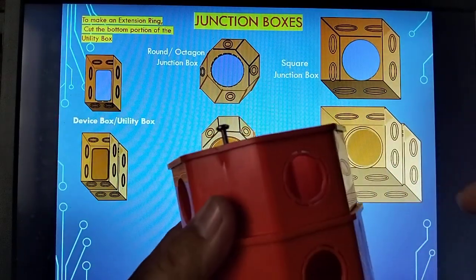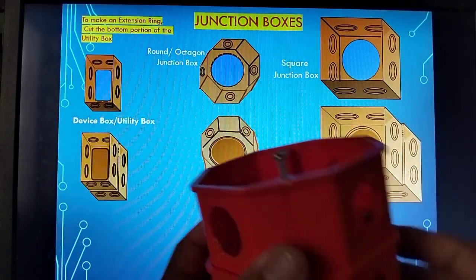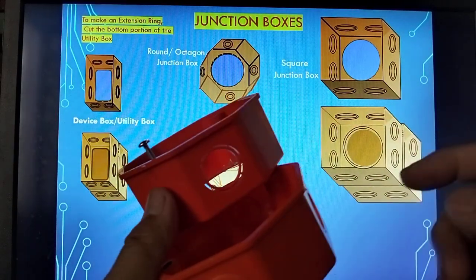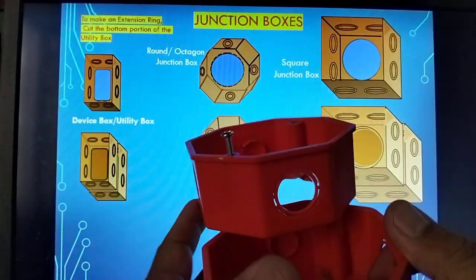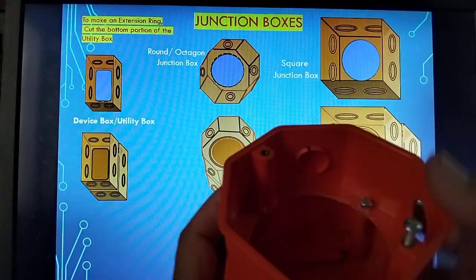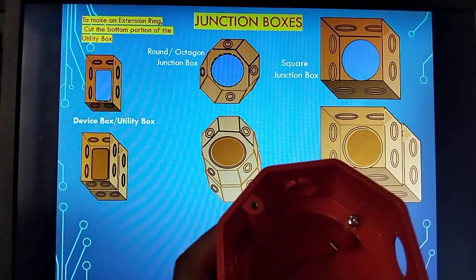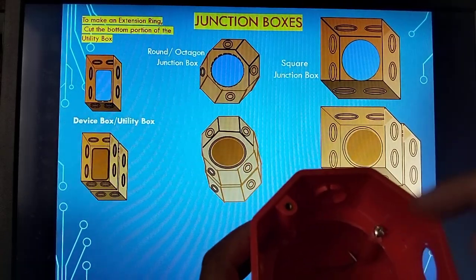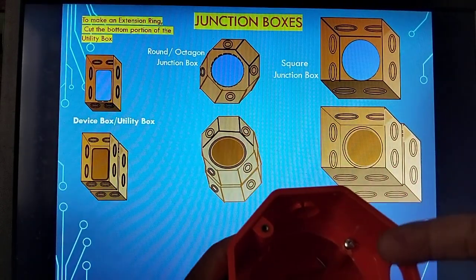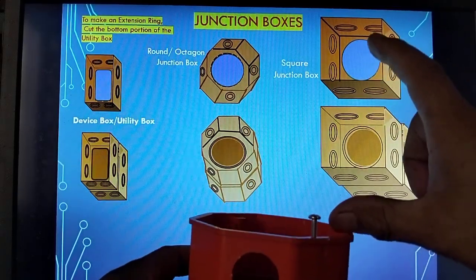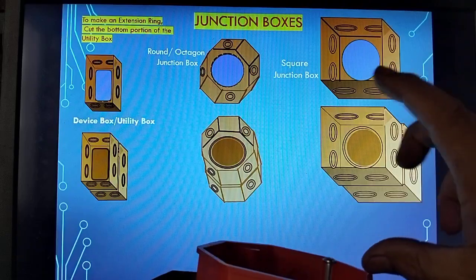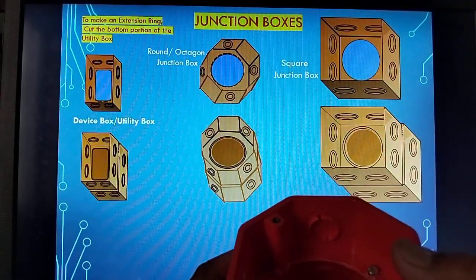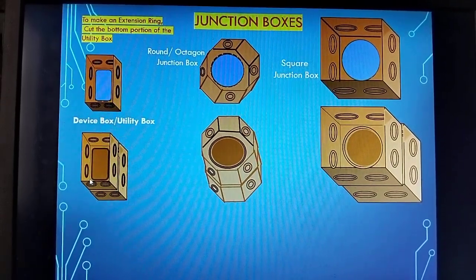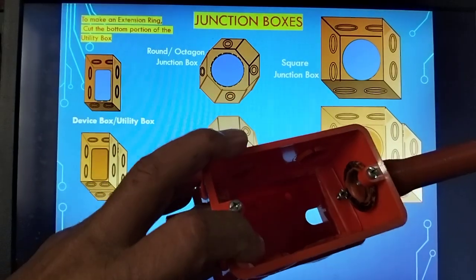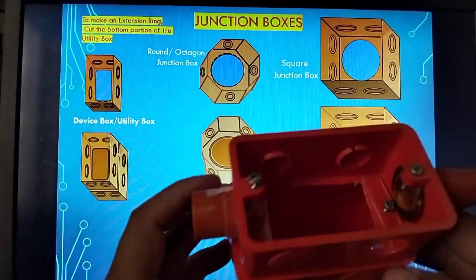Even though you are connecting all, let's say all PVC conduit are already connected here, if you use the extension ring, you can increase the capacity of the junction box even if it is in the same position or the same area, but make sure you have adequate allowance of extended wires for the splicing, wire splicing or wire connection. Same as on the utility box, like this, no? Like this one, you extend.